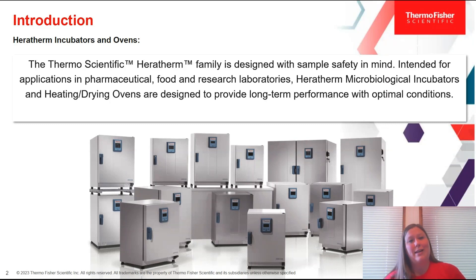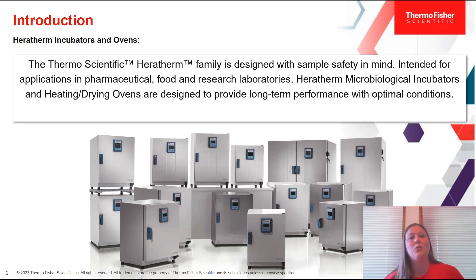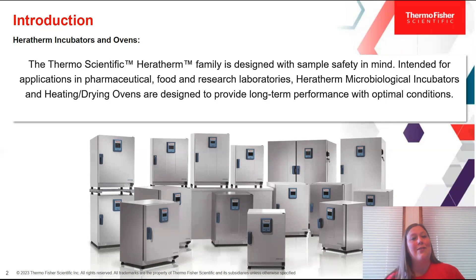Mechanical convection is available in incubators and in ovens. A really special type of convection offered only in the microbiological incubators line is dual convection. It's a unit that comes with a fan so you can leverage mechanical convection when needed, but you can also completely turn that fan off. So if you have an application that requires gravity convection or a really sensitive sample, you can utilize that functionality.